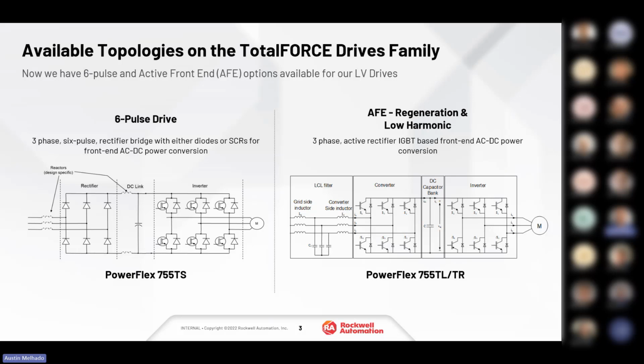What does this allow us to do with the harmonics? Well, typically, if we had harmonic issues, we would put a 3 or more likely a 5% line reactor on the front of this drive. But with this technology built into the VFD itself, thus the 6 IGBTs and the companion LCL filter, we're able to mitigate those low harmonics within the VFD itself.